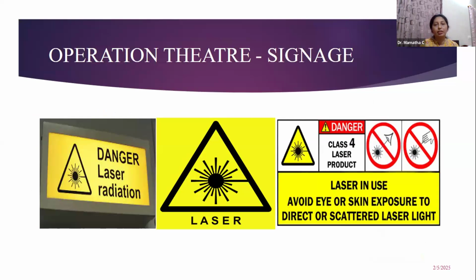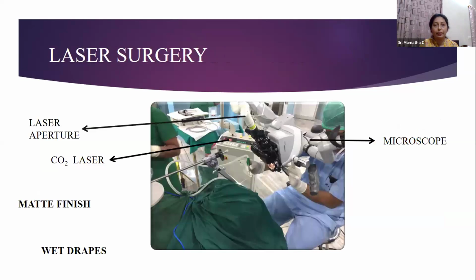These are some of the signages you see on the operating theater door or the wall. The laser surgery should be done in a designated OT, and this sign gives a warning. It informs everyone that the laser is in use and should be entered with the protective measures. This image is taken from a laser surgery OT. Here you can see the surgeon is operating under the microscope and he is using carbon dioxide laser, and the instruments are matte or dull finish to prevent reflection of the laser light to the non-targeted tissue, and the patient is covered with wet drape to reduce the risk of fire.